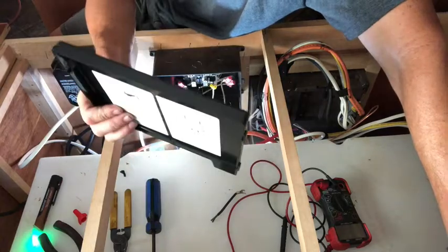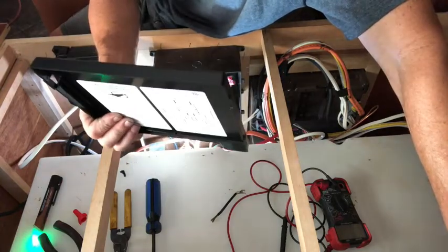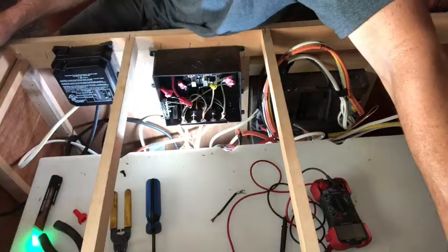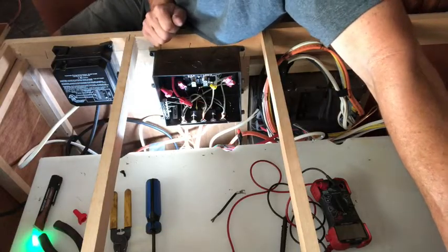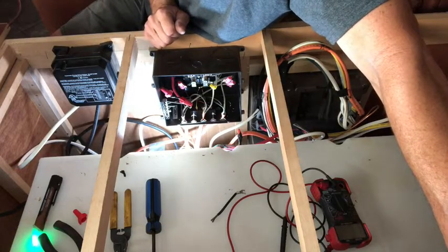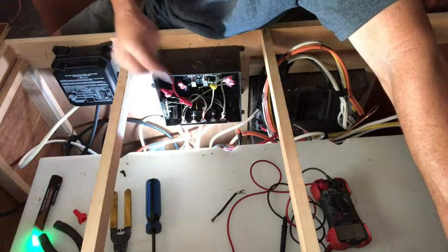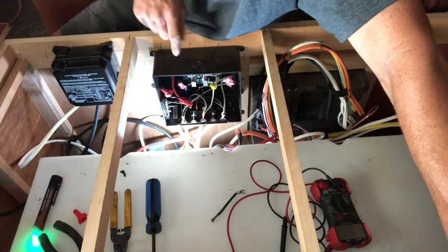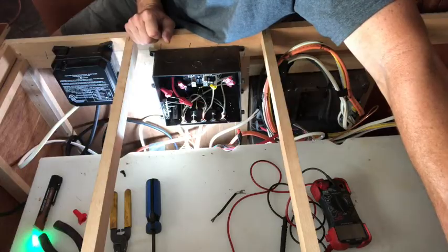doesn't have a seal on it, because then it would get too hot, so you can't really seal it. So get a little bit of moisture in there, and I bet those contacts have corroded. That's my guess at this point, seeing that I have power coming into the transfer switch and no power coming out of the transfer switch.